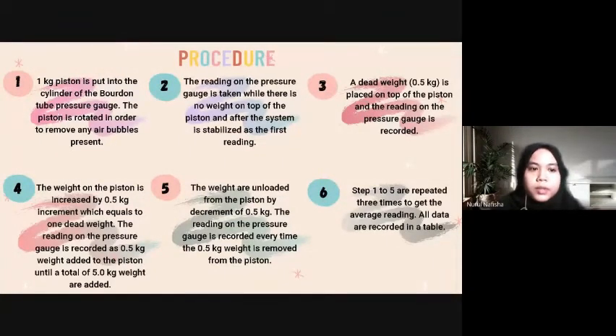The first step is the 1 kilogram piston is put into the cylinder of the Bourdon Tube Pressure Gauge. The piston is rotated in order to remove any air bubbles present. Second step, the reading on the pressure gauge is taken while there is no weight on top of the piston and after the system is stabilized, as the first reading.